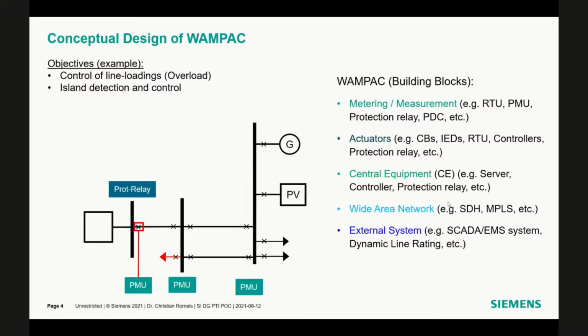But you can also incorporate new measurements, PMU devices or RTUs as a building block. Then you have actuators as a building block. Maybe you can use controllers of the generators. For example, you can maybe also incorporate signals from PMU to the power system stabilizer in case of conventional generation. In case of photovoltaic, for example, you have the ability to curtail these if it's needed, and you also have the under frequency relays for load shedding.